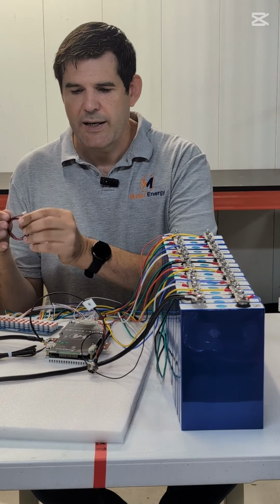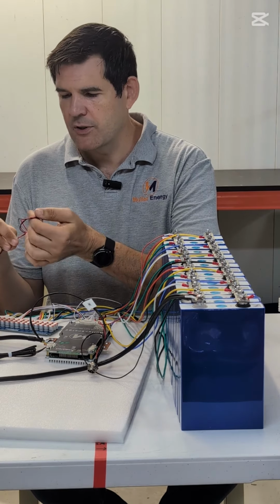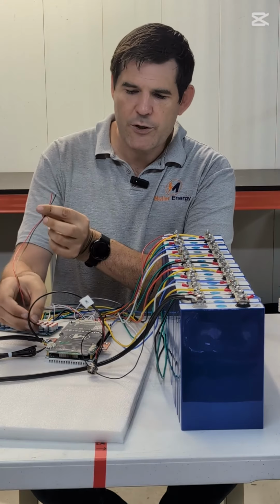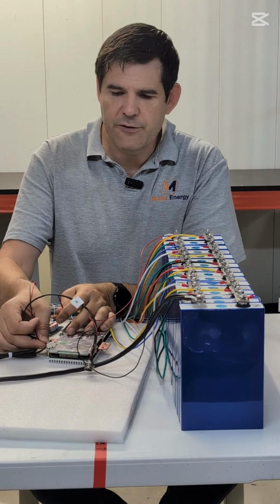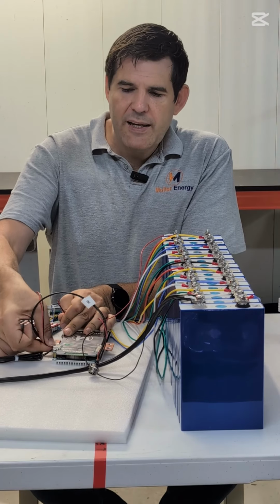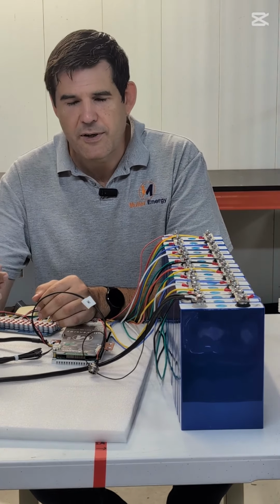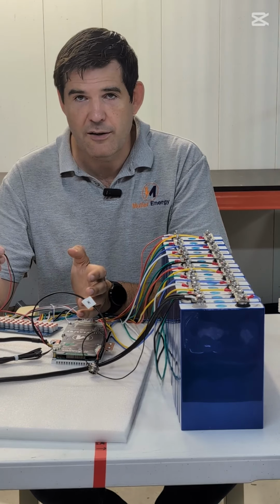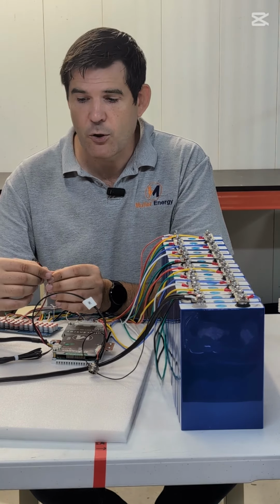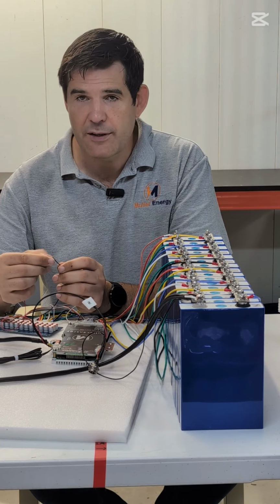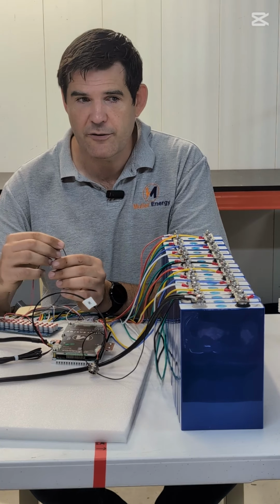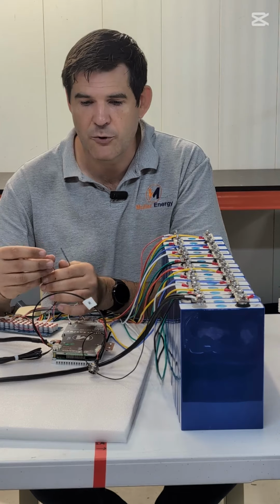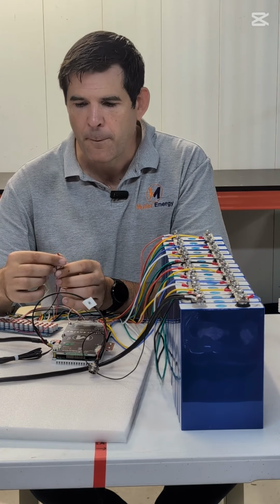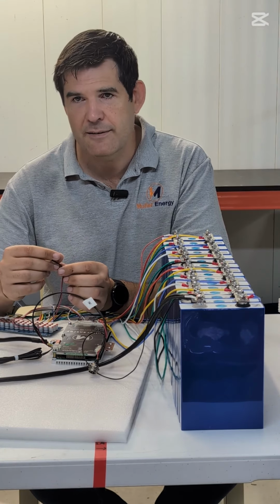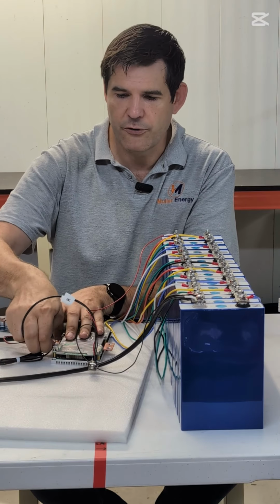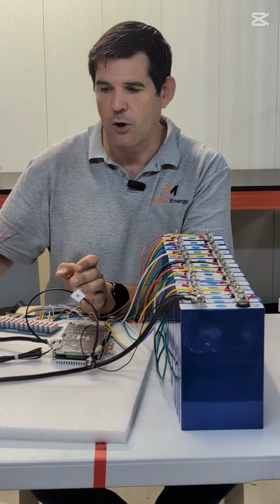The other thing we have is an optional discharge switch, which connects where it says discharge switch. Under function settings there's a function called switch function, which you can have on or off. If it's on, the BMS will only discharge if these two wires are connected, so you could use a push button or something similar. However, I tend to recommend not using that, and keeping the switch function switched off.